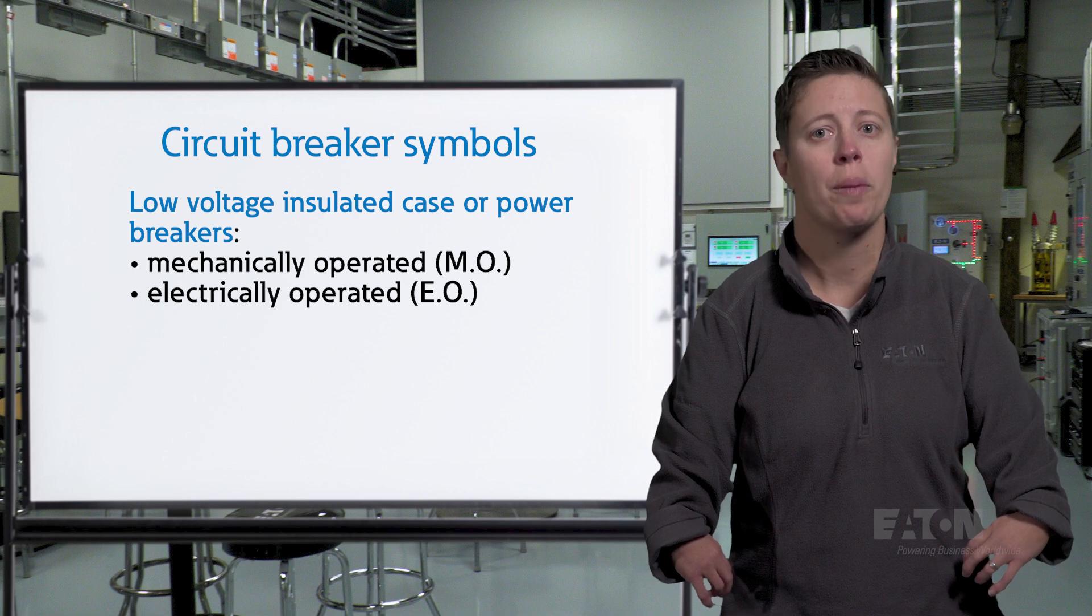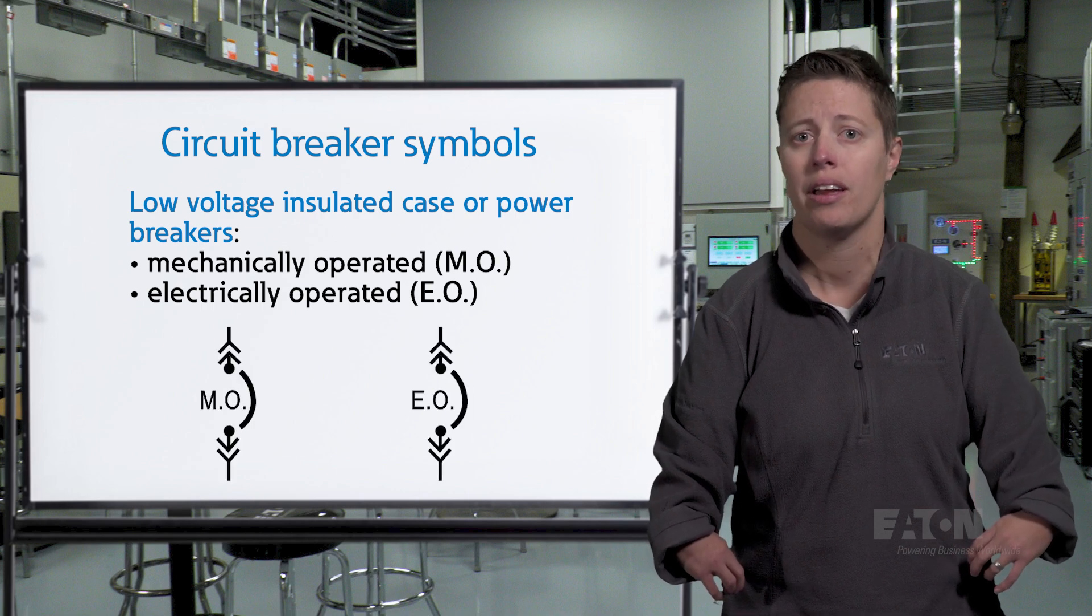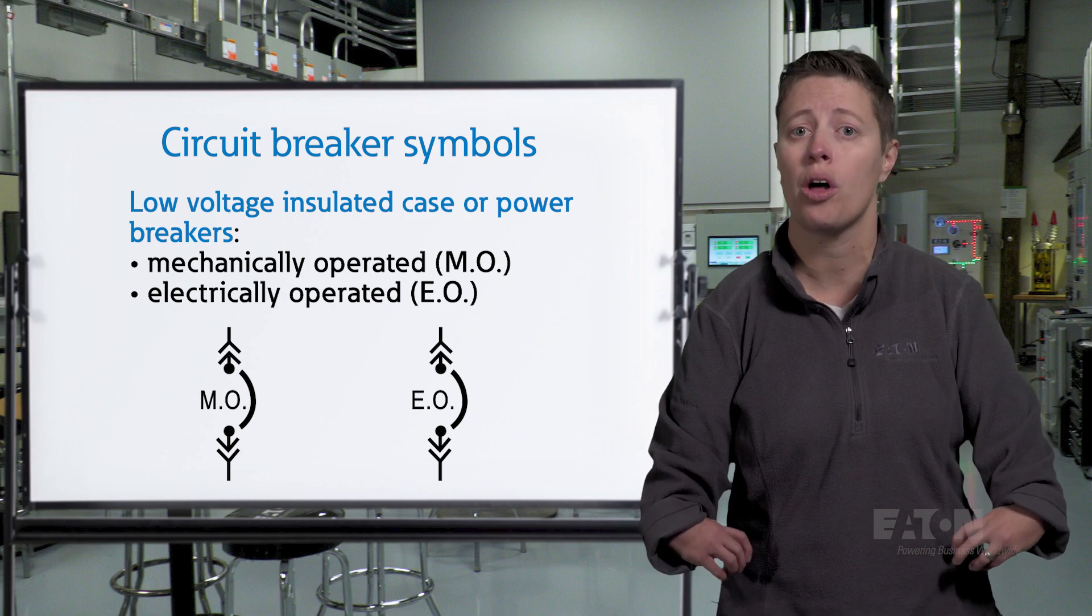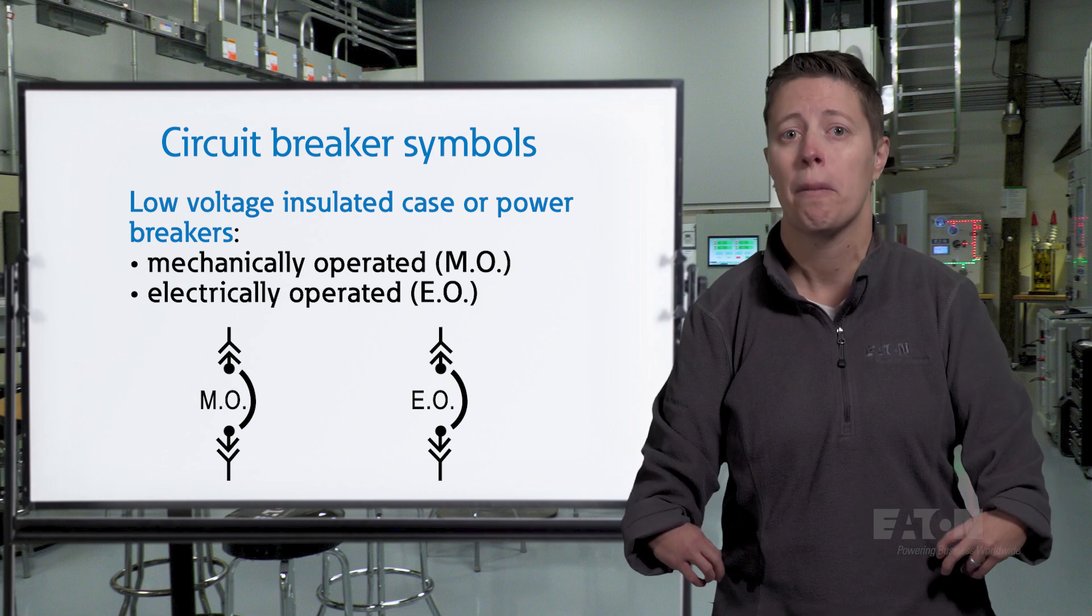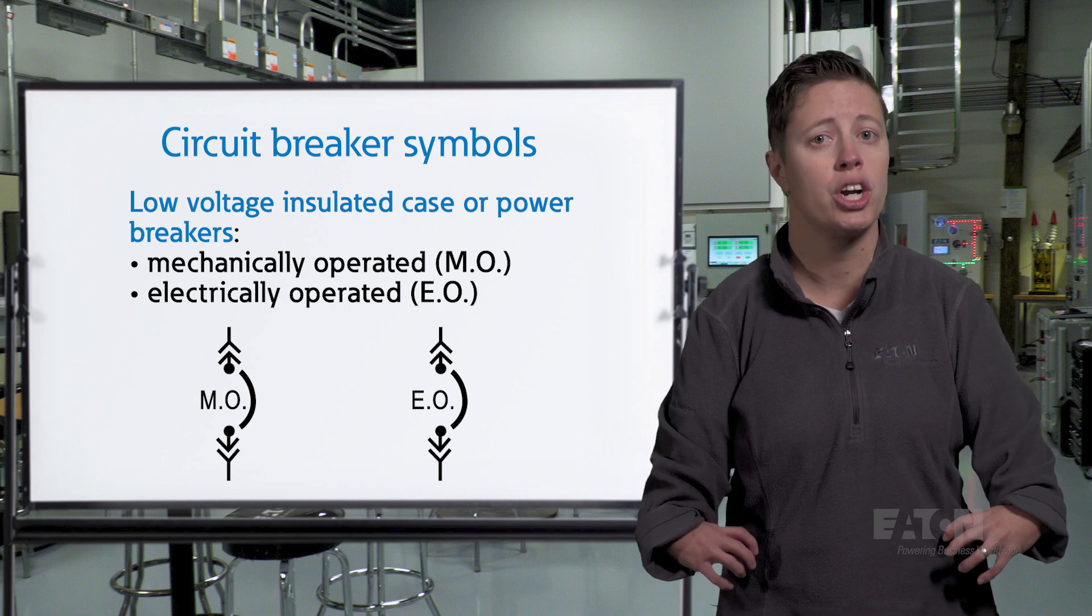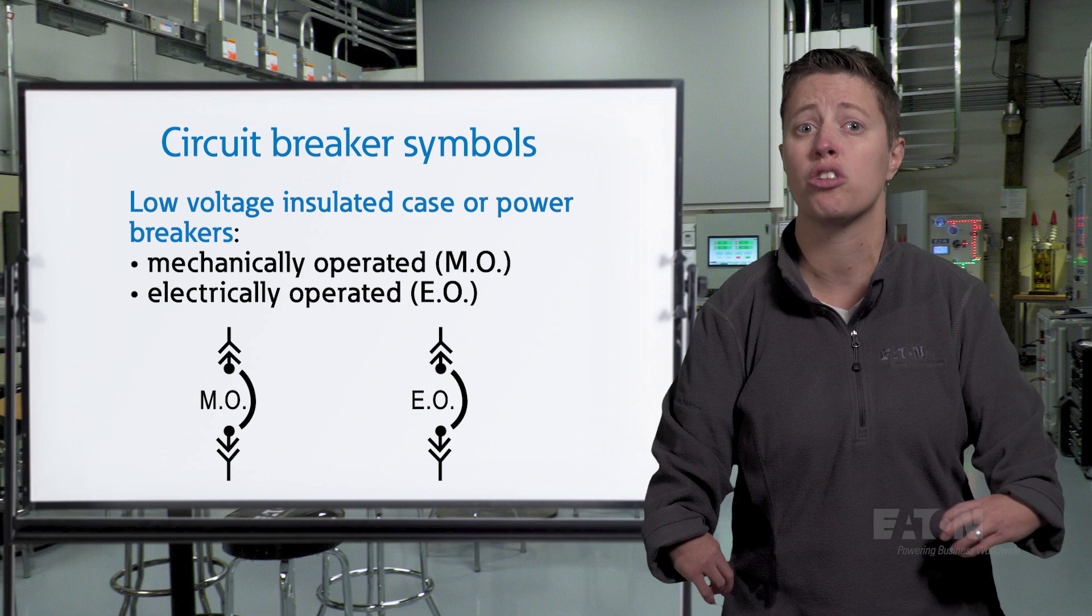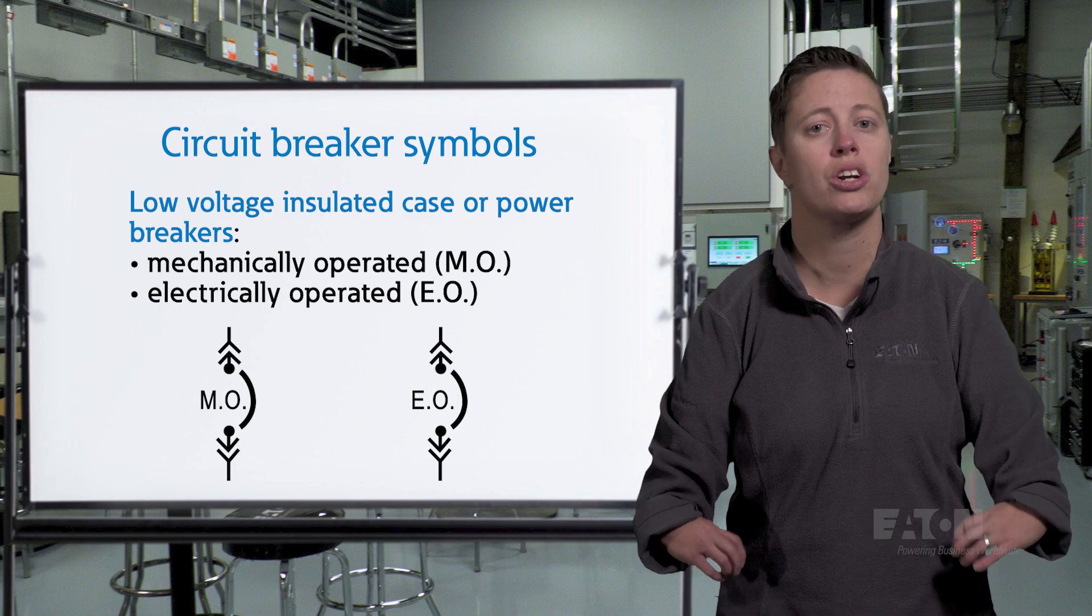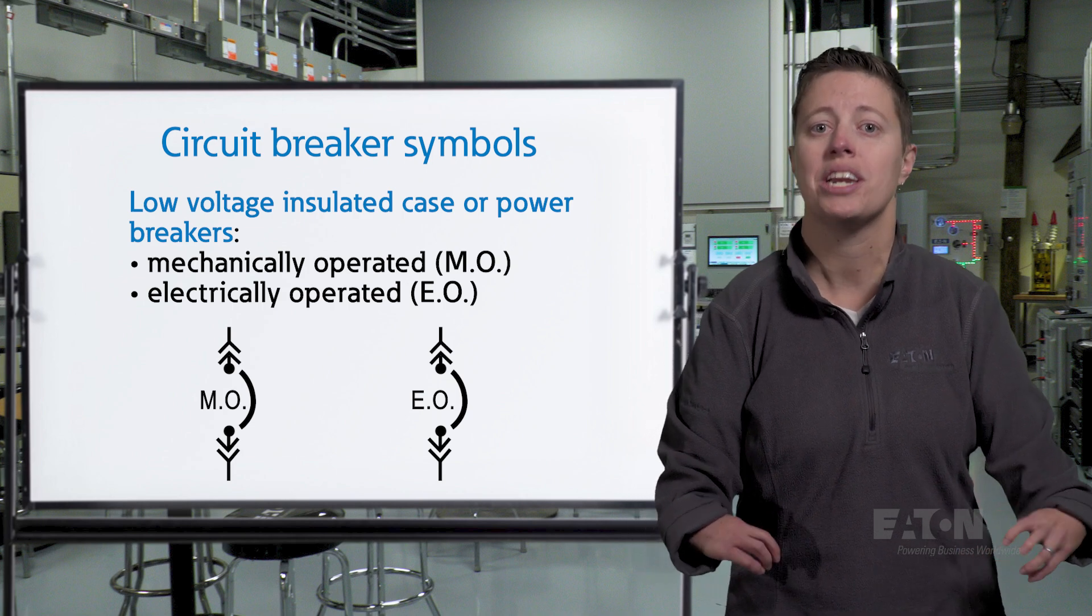Low voltage insulated case or power breakers may be mechanically or electrically operated, and this may be indicated on the drawing. Mechanically operated breakers can only be opened by the integral trip unit or opened or closed by a person interacting with the front of the breaker, and may be indicated by the designation MO for manually operated. Electrically operated breakers include a shunt trip allowing the breaker to be opened from an external signal, and a spring release allowing the breaker to be closed from an external signal. The external signal may come from a push button, control switch, or other protective device. Electrically operated breakers may be indicated by the designation EO.